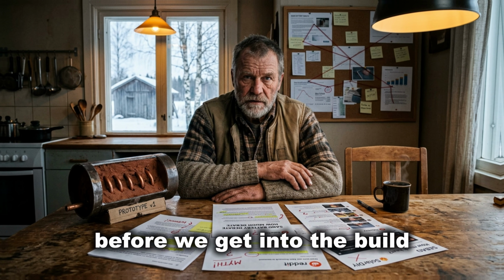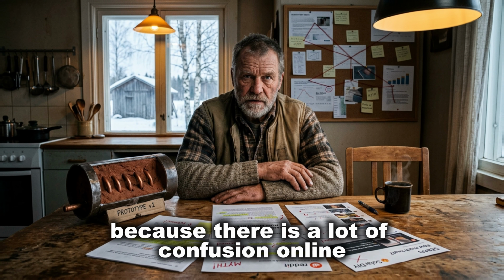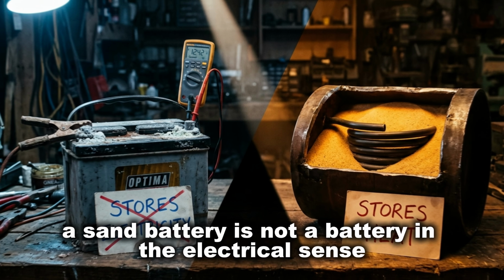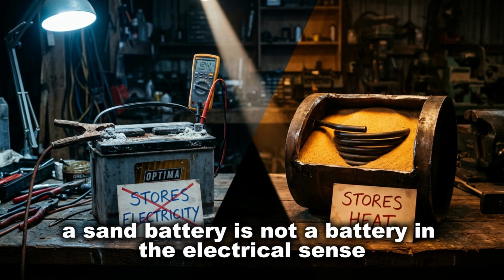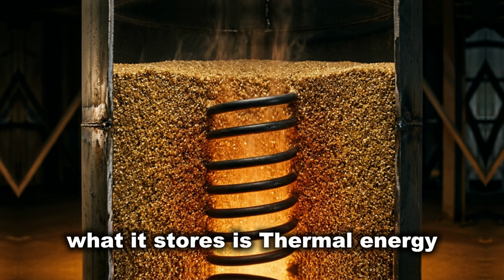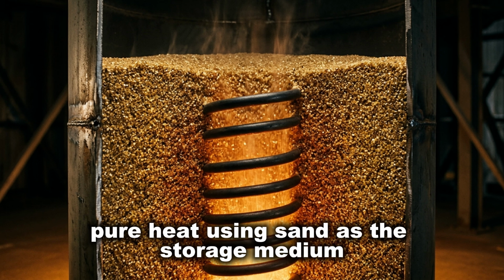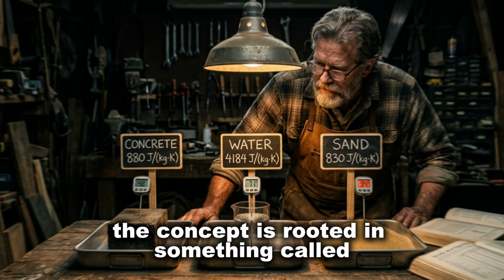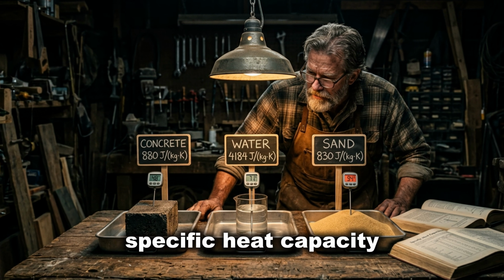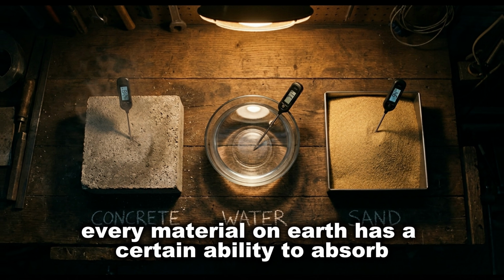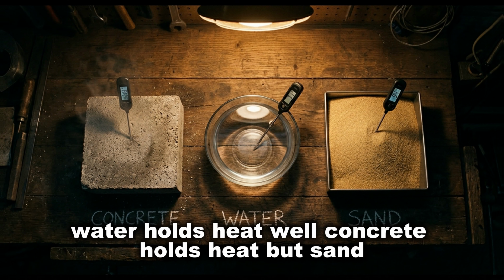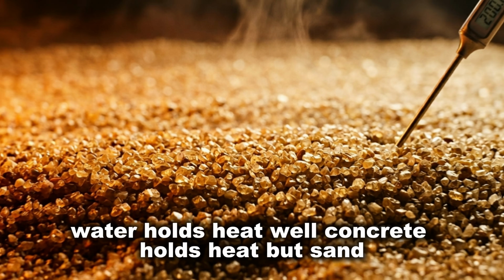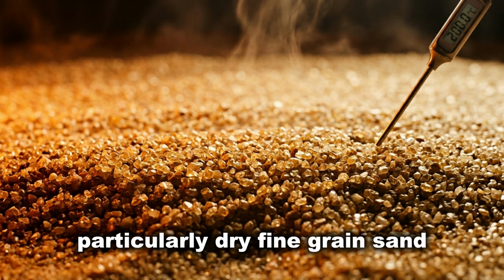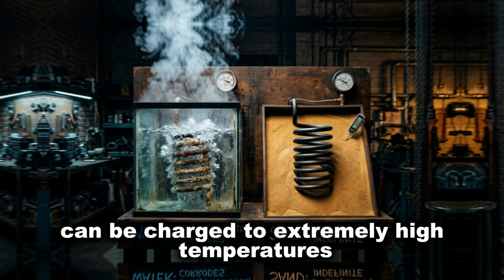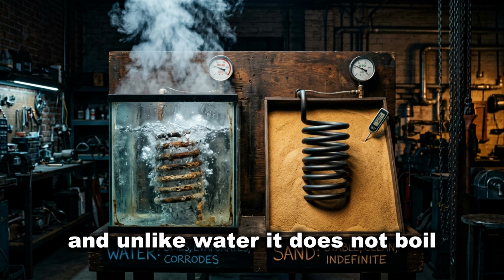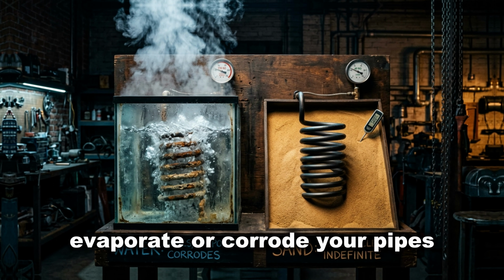Before we get into the build, let us talk about what this actually is, because there is a lot of confusion online. A sand battery is not a battery in the electrical sense. It does not store electricity. What it stores is thermal energy, pure heat, using sand as the storage medium. The concept is rooted in something called specific heat capacity. Every material on Earth has a certain ability to absorb and hold heat. Water holds heat well, concrete holds heat, but sand, particularly dry, fine-grained sand, holds heat exceptionally well, can be charged to extremely high temperatures, and unlike water, it does not boil, evaporate, or corrode your pipes.